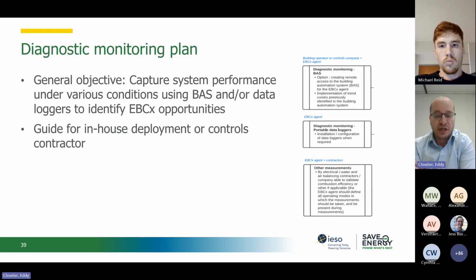Having remote access to the BAS system is always also an asset that will facilitate many existing building commissioning tasks. And basically, we are always trying to obtain this access. But depending on the client and the sector, I would say this is not always possible or easy. There is a certain fear that the system might be used in a bad way or a breach of access, and also limits depending on the type of building. For example, for a building in the national defense sector, you can try to have the remote access, but generally it's very hard to obtain.